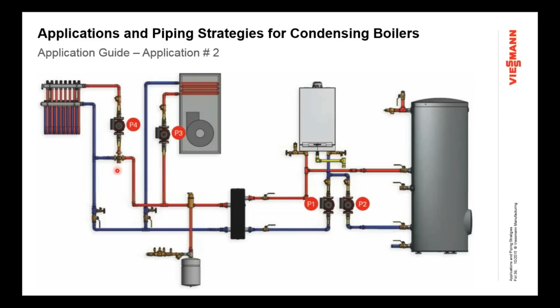So that thermostatic valve, we can set that to whatever. This is a 1 temperature set point device, so I may set that at, say, 110 Fahrenheit. So even though the boiler is generating a higher temperature and the fan coil gets that higher temperature, I'm protecting the floor from overheating, and I'm giving the floor the temperature it needs to satisfy its requirements.